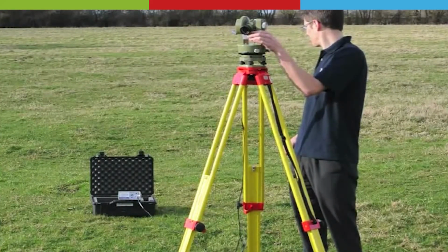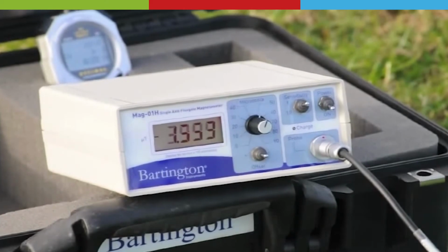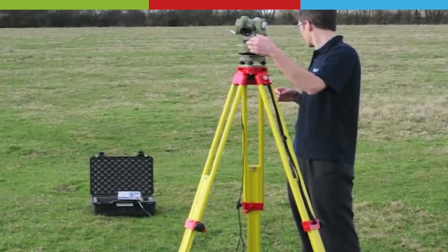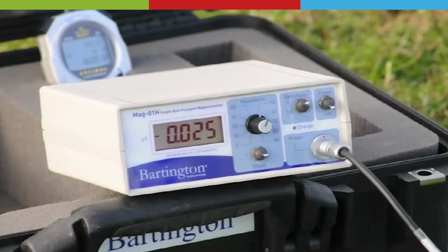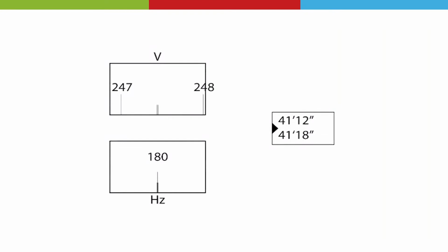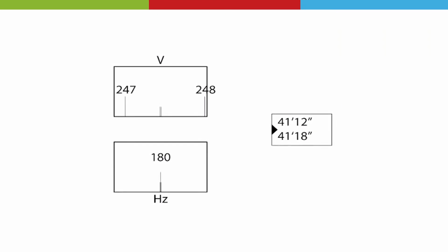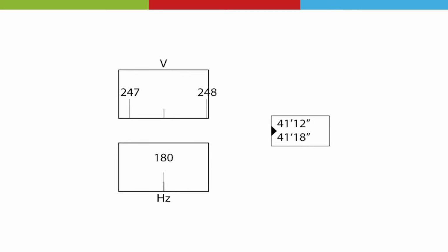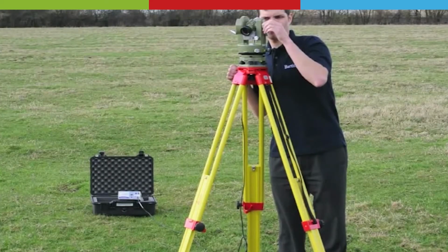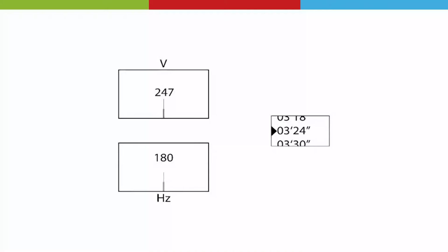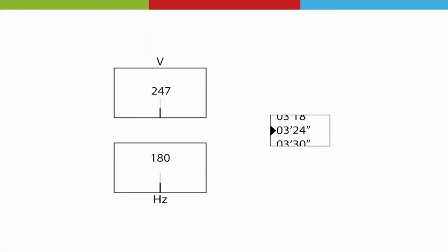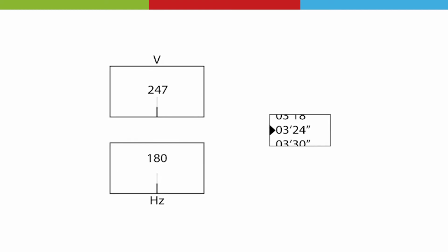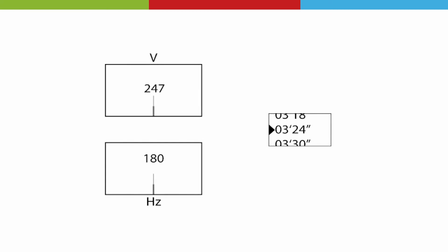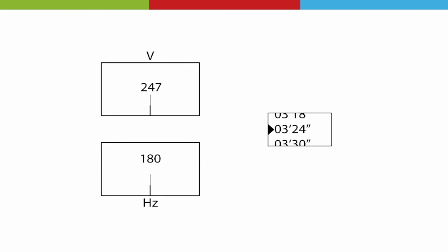Rotate the theodolite on the vertical circle until the magnetometer reads 0. Adjust the theodolite by hand and then fine-tune with the vertical circle drive. The scale window will not be adjusted for vertical readings and will look like this. Because the theodolite is pointing south with the probe down, you now take your south down reading. Adjust the vertical scale to its nearest whole number using the micrometer screw. In the example shown here, the south down reading is 247 degrees, 3 minutes, 24 seconds.